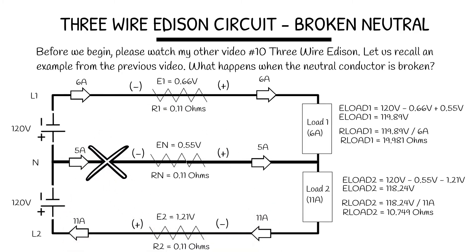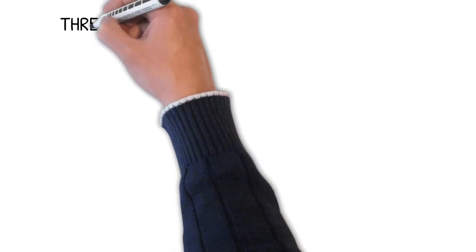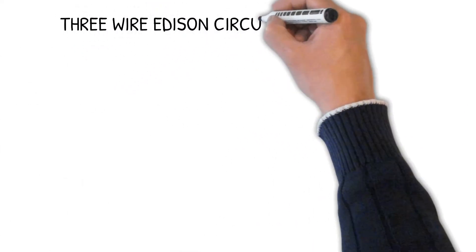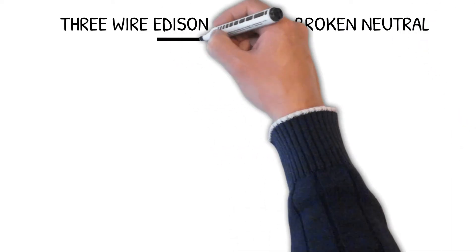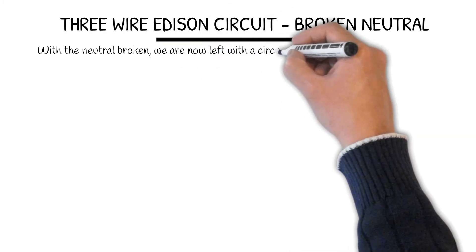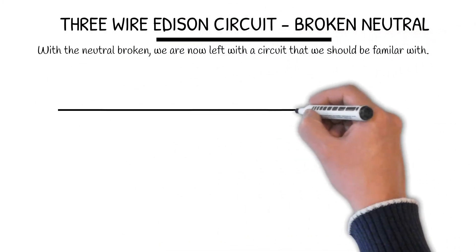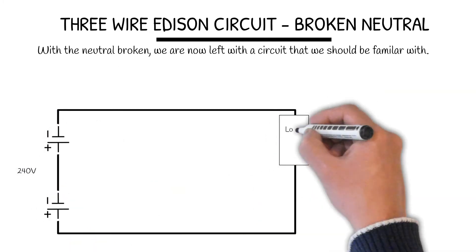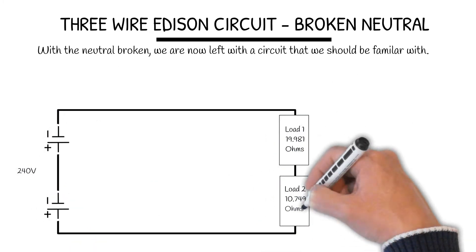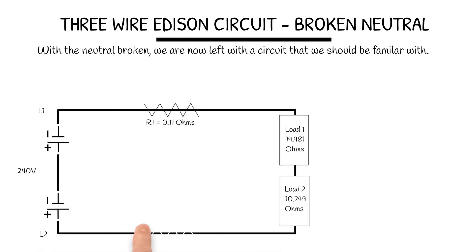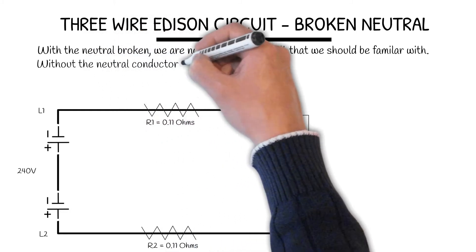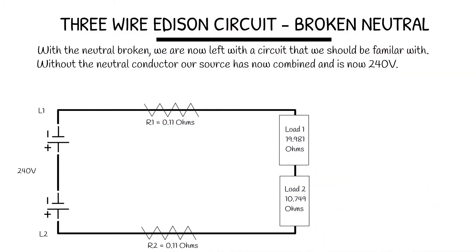With the neutral broken, I mark with an X on this conductor. 3 Wire Edison Circuit Broken Neutral. With the neutral broken, we are now left with a circuit that we should be familiar with. Without the neutral conductor, our source has now combined and is now 240 volts.